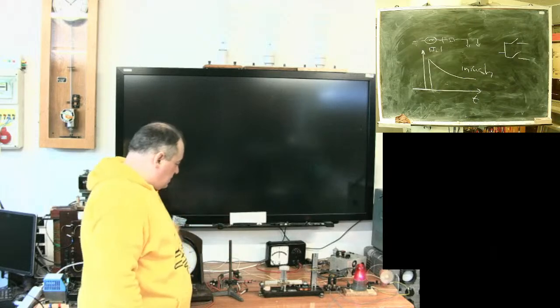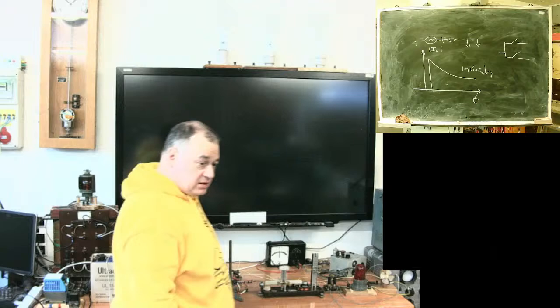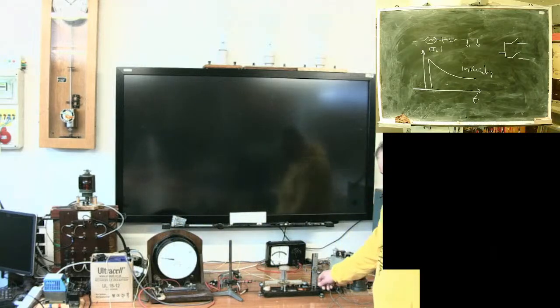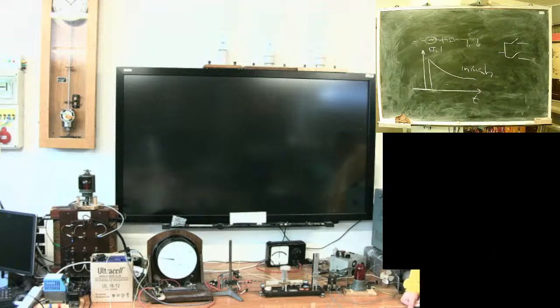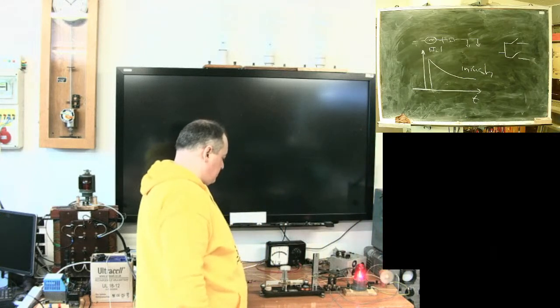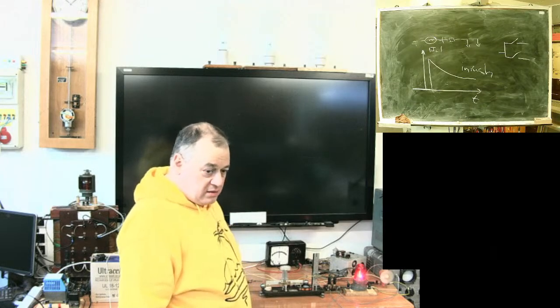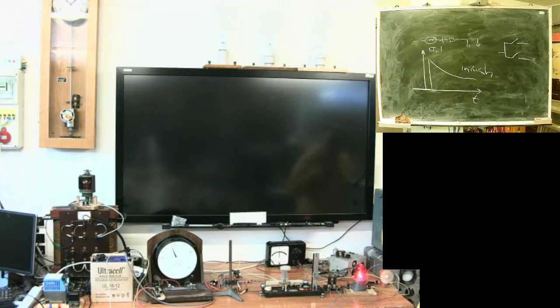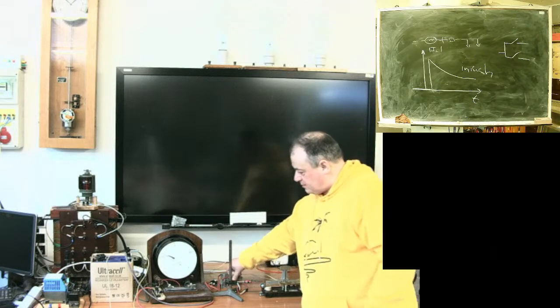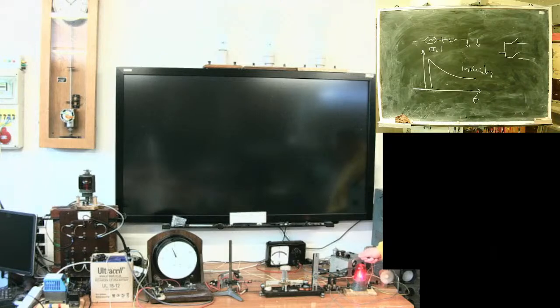Again, this. I started with the wrong setup. What do I need? Increase the trip current. I have increased the current. What now? No false operation. Very nice. Now I make a short circuit. Yes, it's a fault. Oh, trip signal. This is correct operation of protection, yes?